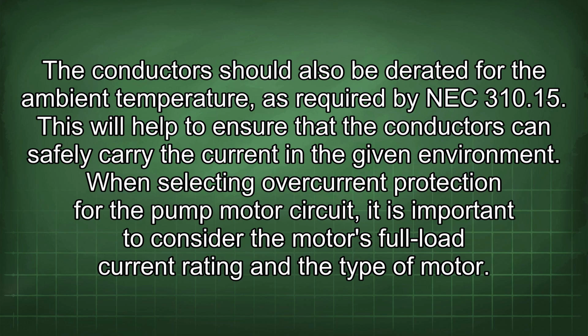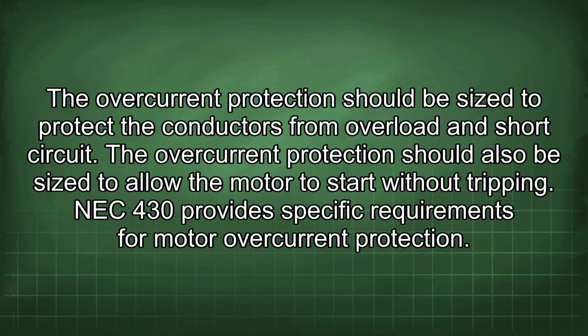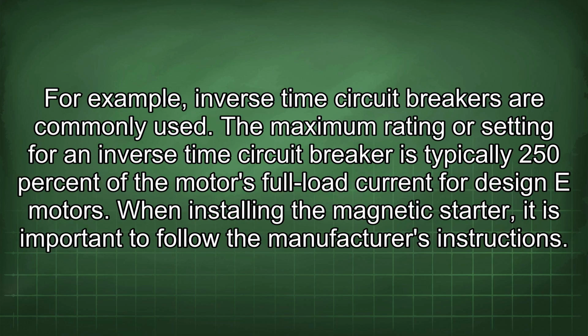When selecting overcurrent protection for the pump motor circuit, it is important to consider the motor's full load current rating and the type of motor. The overcurrent protection should be sized to protect the conductors from overload and short circuit. The overcurrent protection should also be sized to allow the motor to start without tripping. NEC 430 provides specific requirements for motor overcurrent protection. For example, inverse time circuit breakers are commonly used.